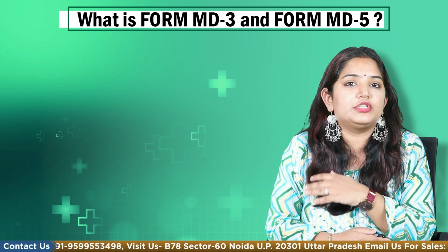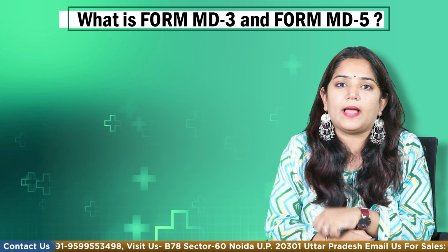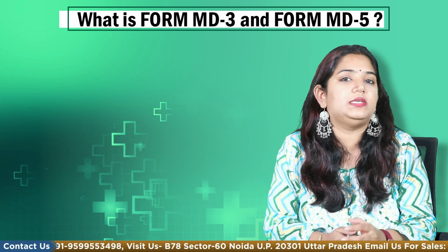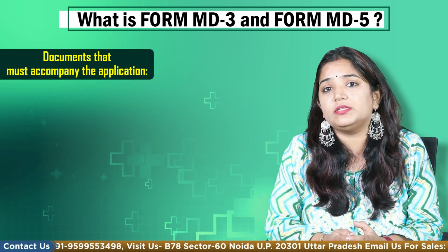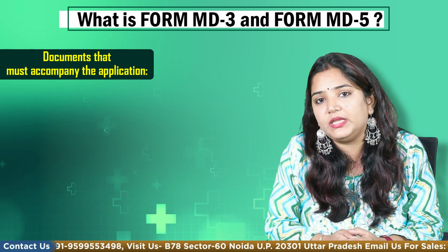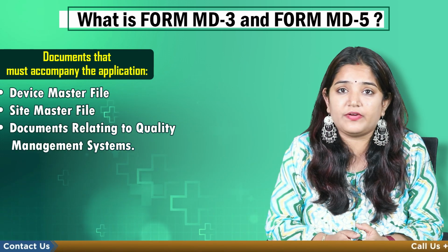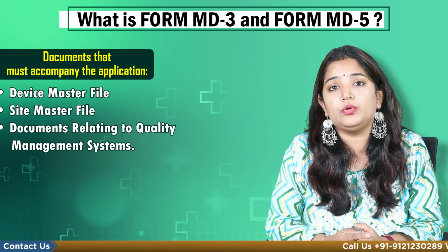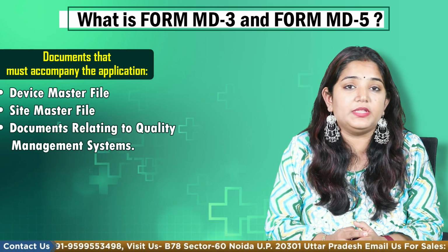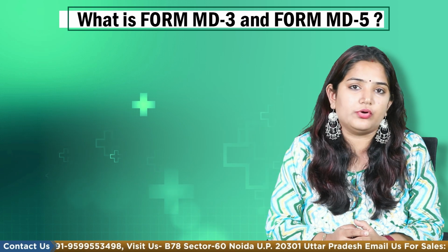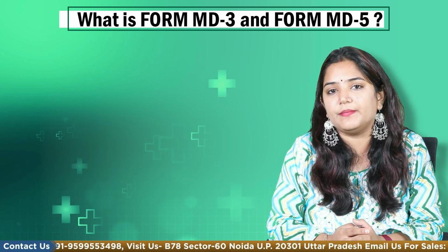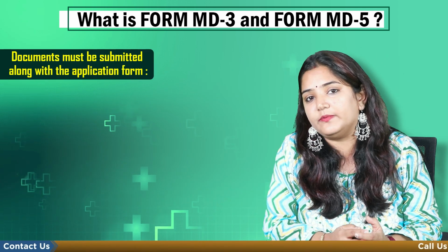Let's see the essential documents required for filing the application. According to the CDSCO, the following are among the documents that must accompany the application: device master file, site master file, and documents related to the quality management system. These three are the most important documents that are required to be submitted along with Form MD-3.